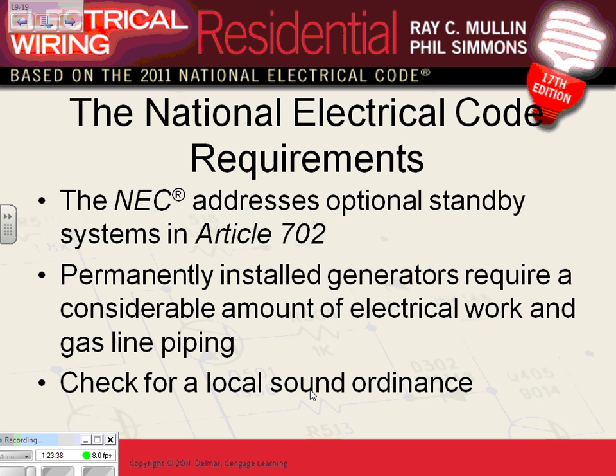Number one, you might need a permit from the city if you have a permanently installed generator. And sound ordinance. A sound ordinance is a big deal. Probably, Chris, you encounter that one, especially when we have bigger diesel generators. They have measurement. The inspector will go measure at the property line, and you have to have, and I'm not going to go with the numbers now, a certain amount of decibels so you don't annoy the neighbors, especially in a residential neighborhood.